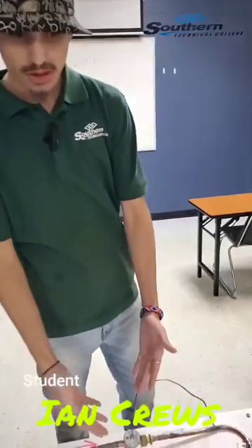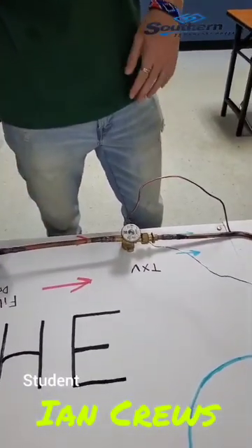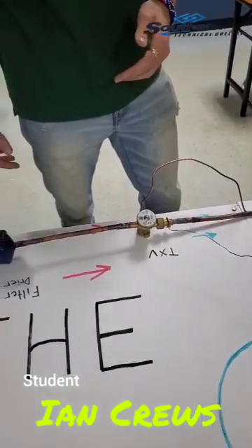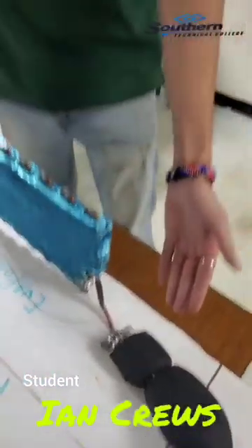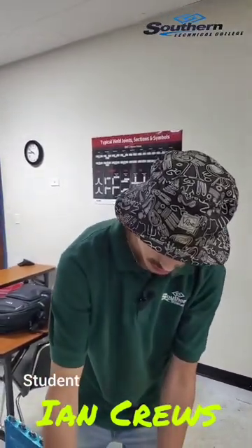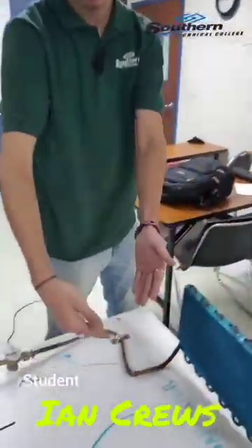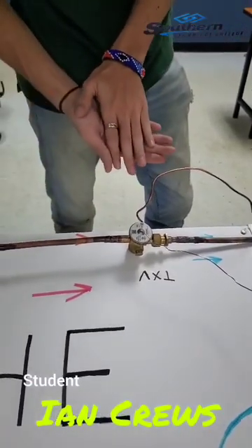And this specific metering device is a TXV. It's a thermostatic expansion valve. And it's got this little sensing bulb that picks up the temperature of the refrigerant coming out of the evaporator. And as temperature and pressure rise and fall together, the temperature of the refrigerant in the suction line shares its temperature with the sensing bulb, and it sends its pressure back to the TXV, having it open more or close less depending on what is needed for sufficient superheat.